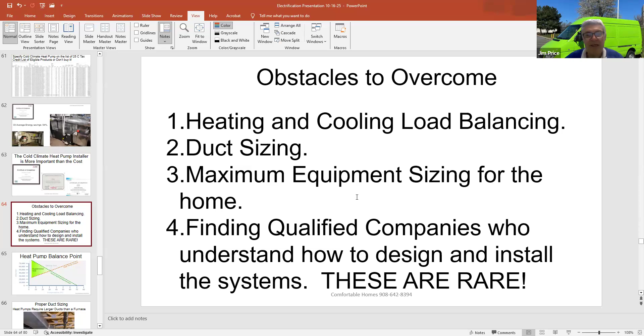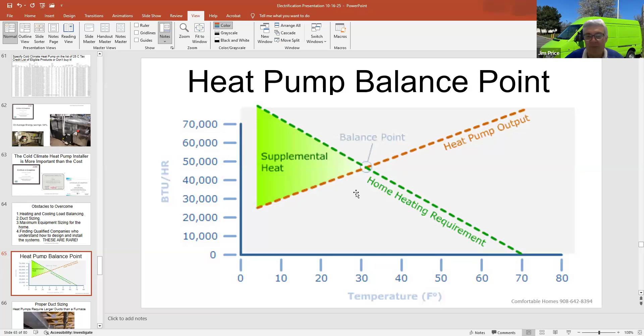The heat pump balance point is we want to be as close to the middle as possible, having a small air conditioner and a just big enough heat pump for the heating requirement. When we size a heat pump, we size for the heating load, but normally in air conditioning, we size for an air conditioning load. So it's important to understand that the heating load is going to be bigger than the air conditioning load. That's the other great thing about these cold climate heat pumps, they are modulating and have inverter technology.